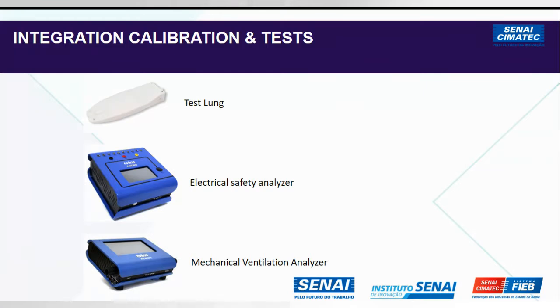Not calibrating a ventilator is very dangerous for patients. It's almost like not having a ventilator. And the electrical safety analysis is necessary to test the chance of discharge and leakage current, which is very dangerous for the patient's heart. It causes fibrillation and damage to the patient. You need a clinical engineer, an electrical engineer, and a specialized technician to perform all the tests to guarantee the safe operation of the mechanical ventilator.